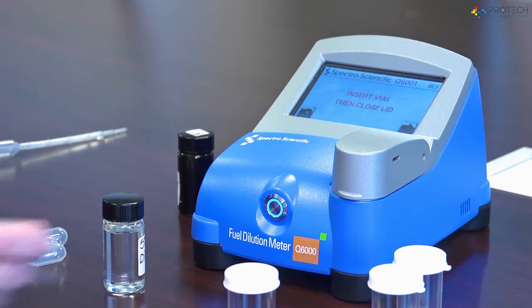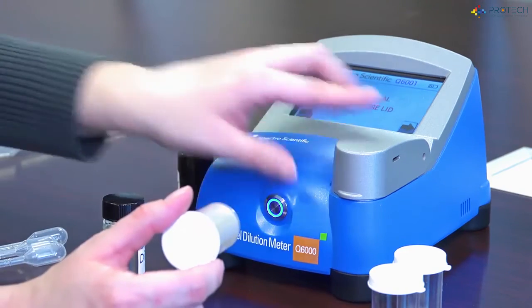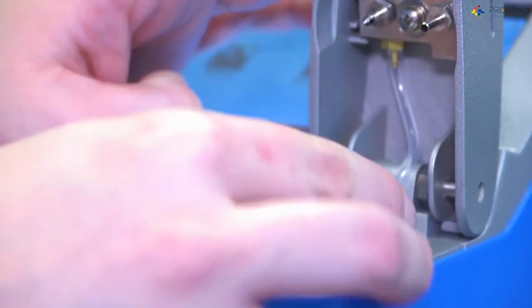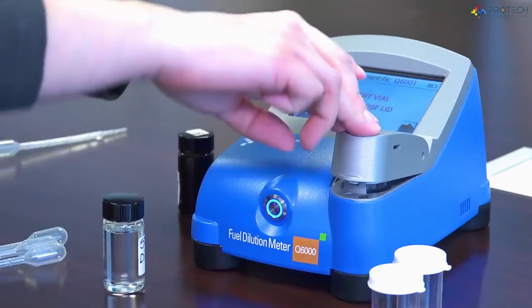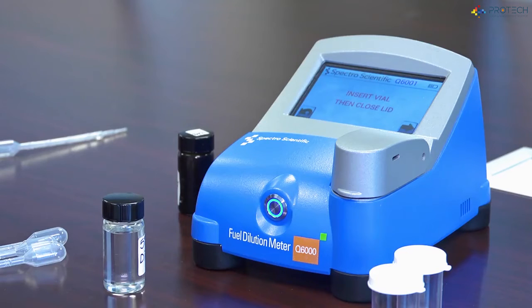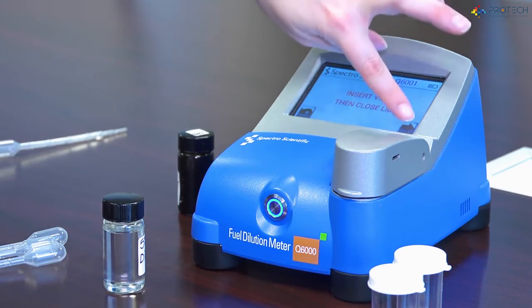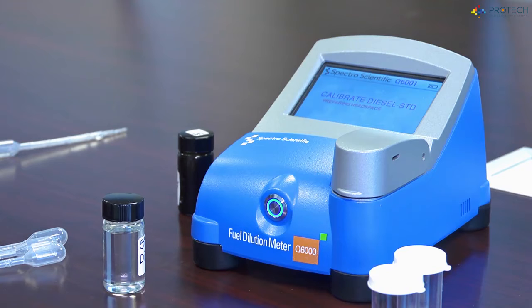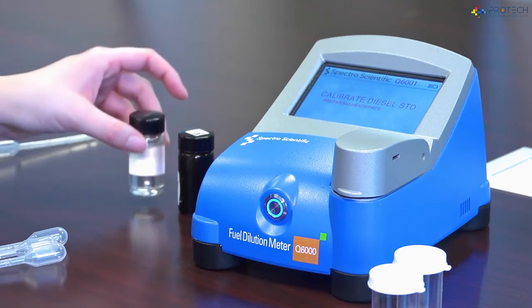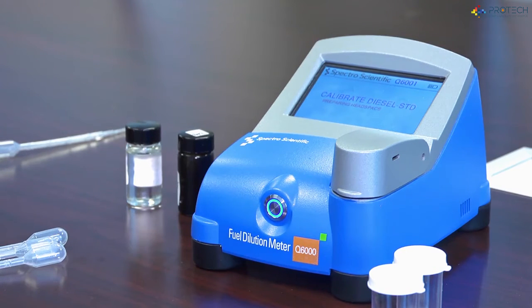So now it's been about a minute, so I can go ahead and run my sample. I'm going to insert the vial, and I'm going to close the lid. I'm going to push it hard so that I punch the cap of the vial. Then I'm going to push next. Preparing headspace. So now it goes. Analysis takes about a minute and a half. Whether you're running a calibration standard or measuring an unknown sample, it takes about a minute and a half.